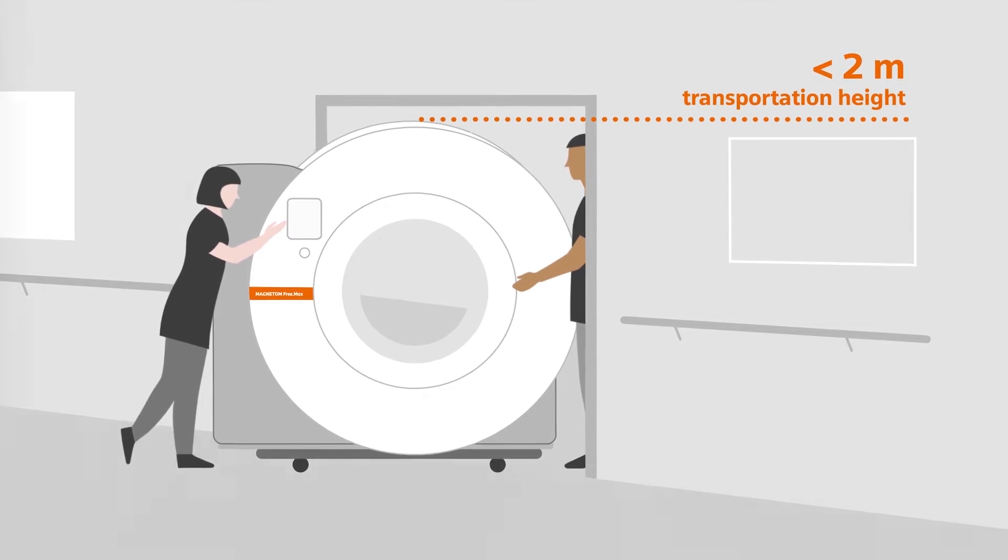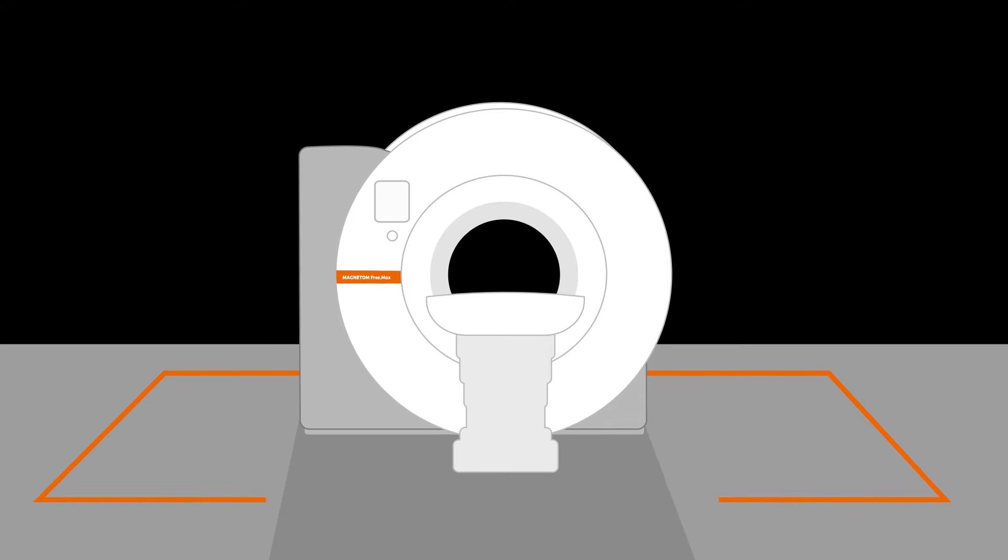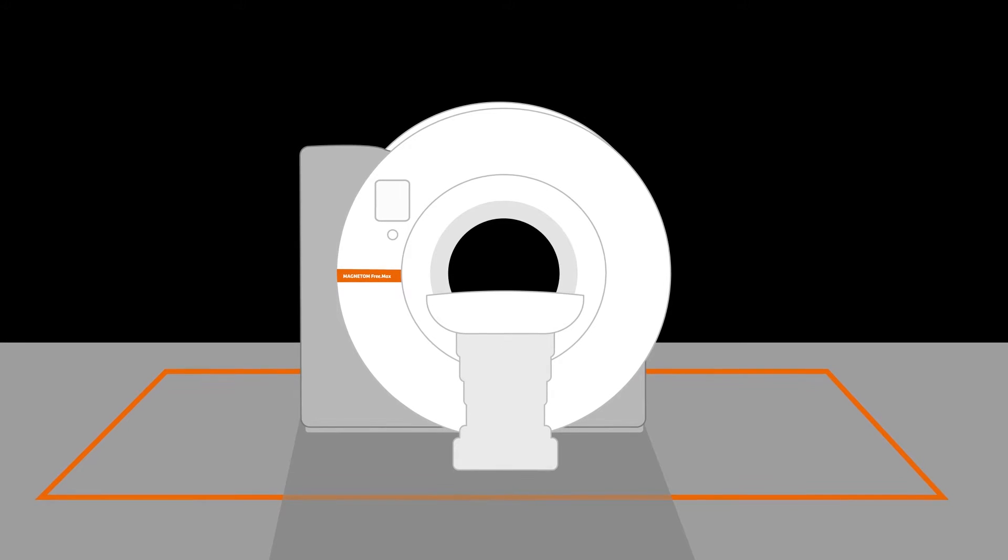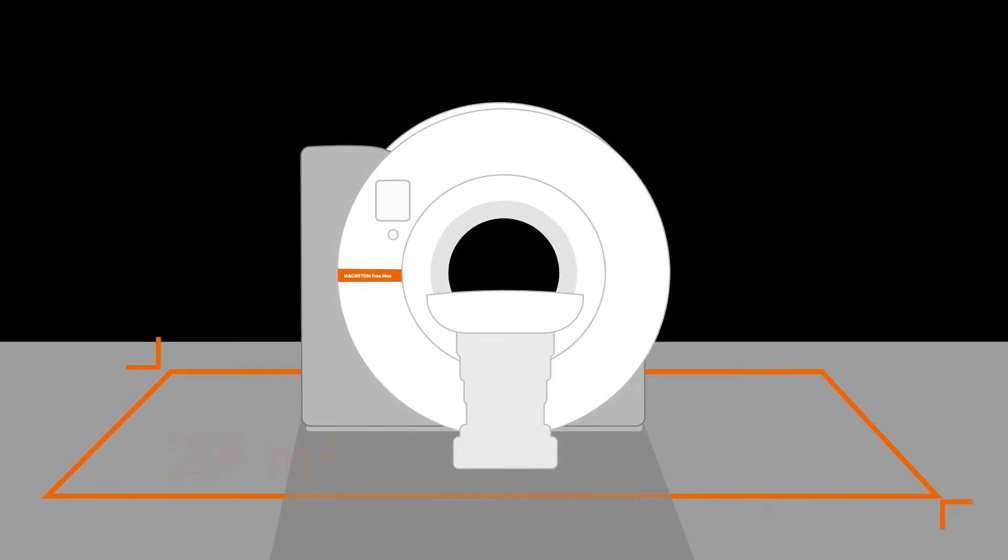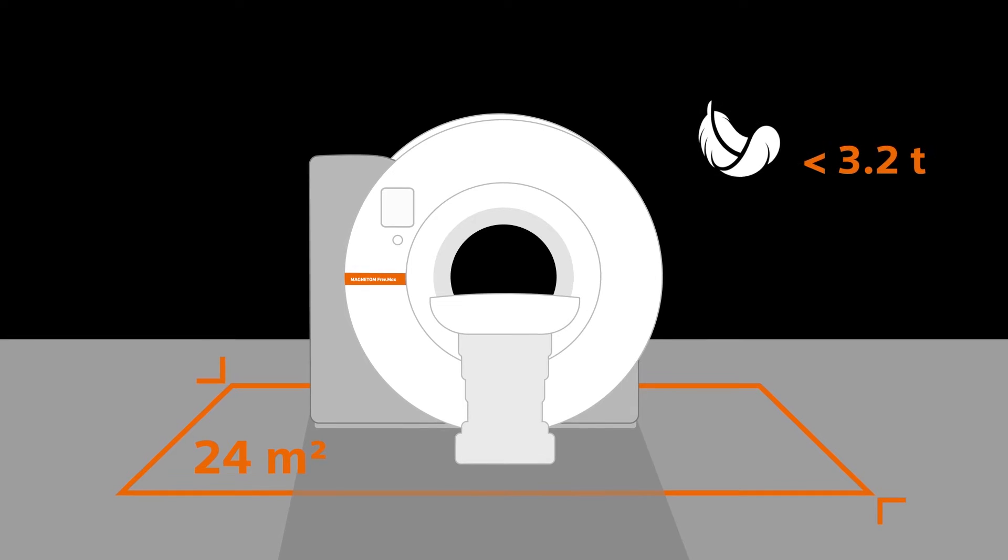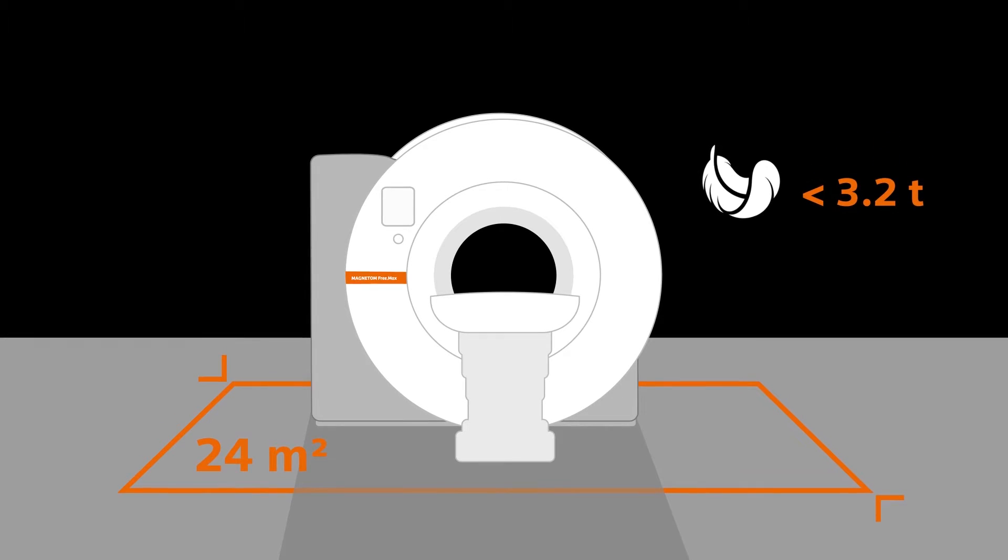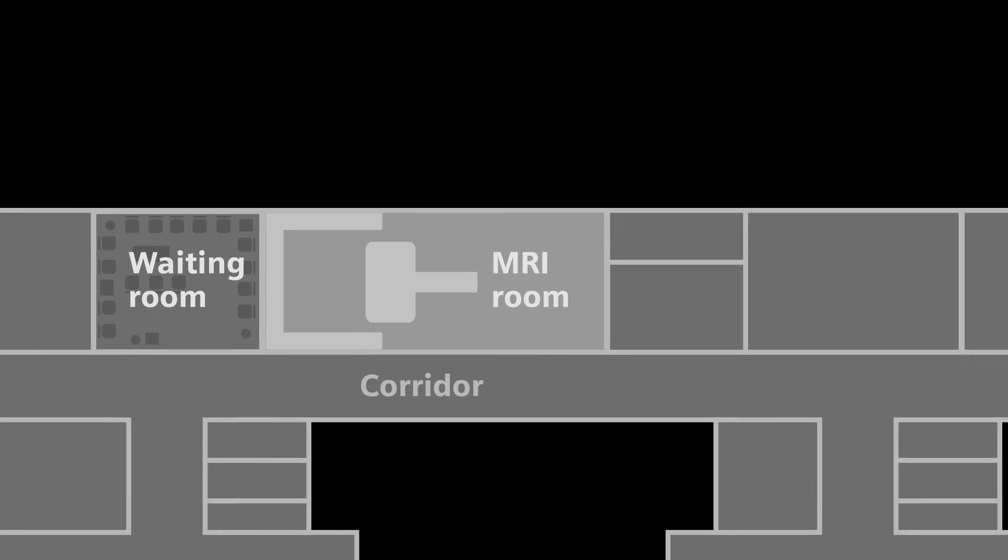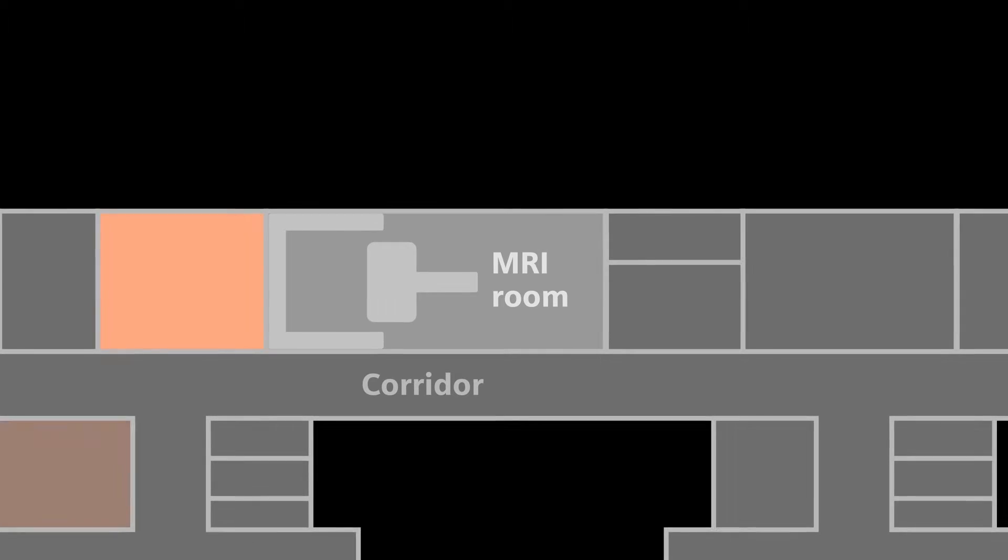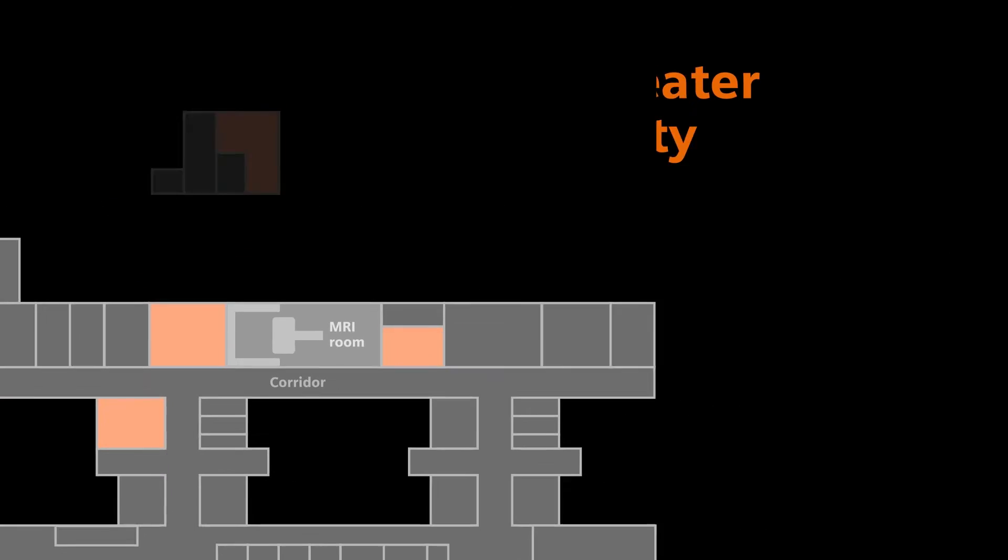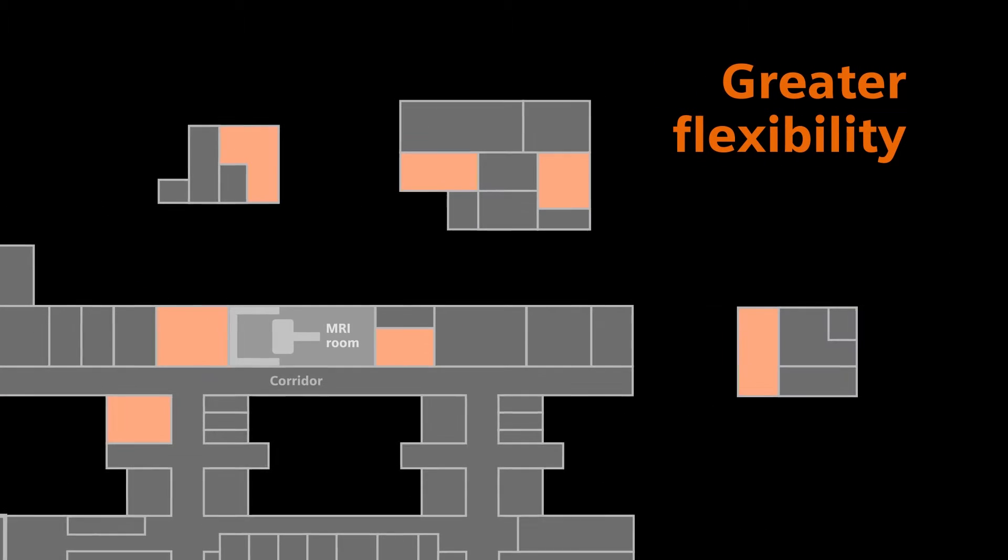The overall system footprint of Magnetom Freemax also sets a new benchmark with only 24 square meters and a floor load of less than 3.2 tons. This greatly reduces room requirements and opens the door to installing MRI systems in previously unthinkable locations.